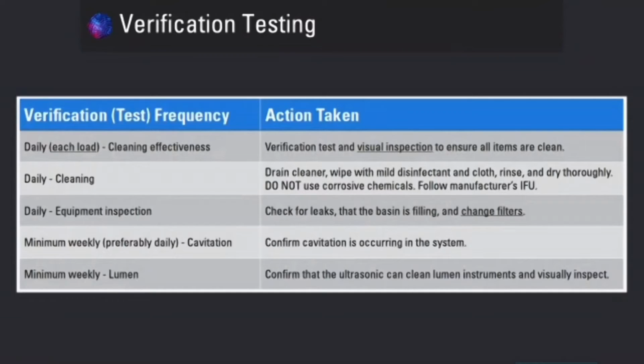Minimum weekly, preferably daily, cavitation. Confirm cavitation is occurring in your system. Remember your speakers, that's creating that sound, that powerful effect. And if they're not happening, they're not cleaning. Okay, so we'll talk a little bit more about that in a moment. And minimum weekly for lumens, confirm that the ultrasonic can clean lumen instruments. And again, visually inspect.